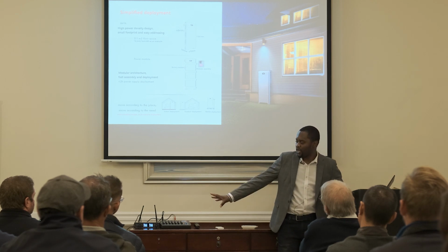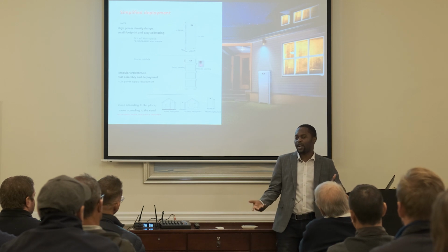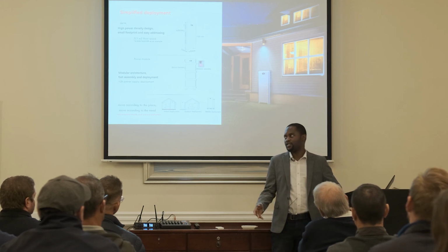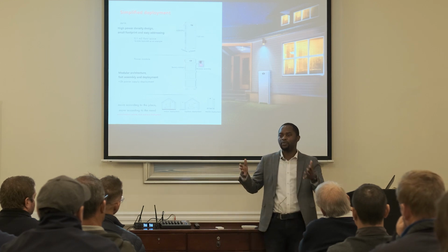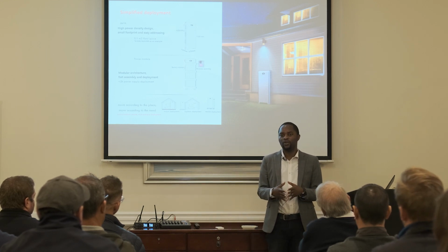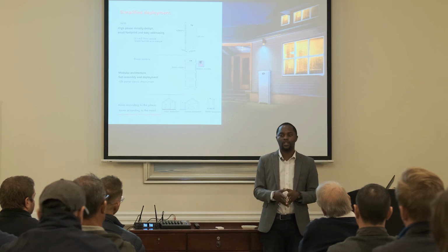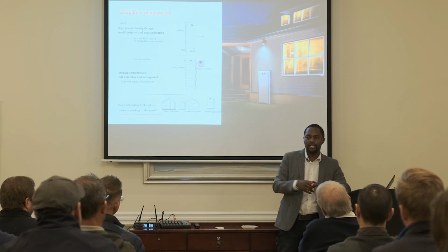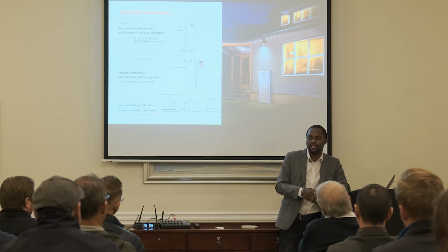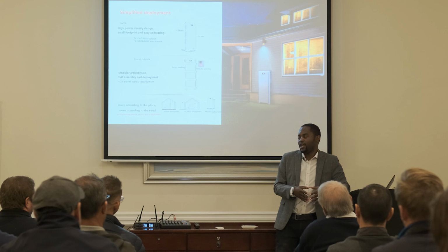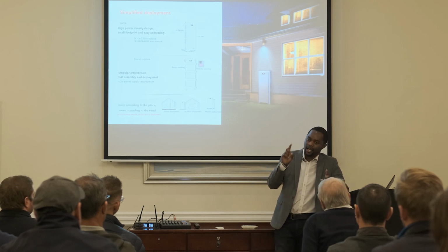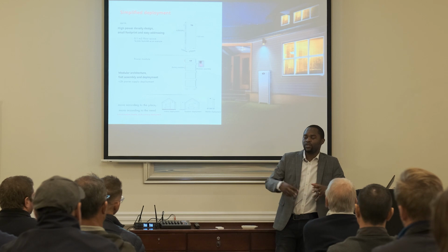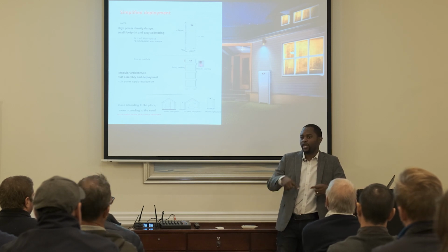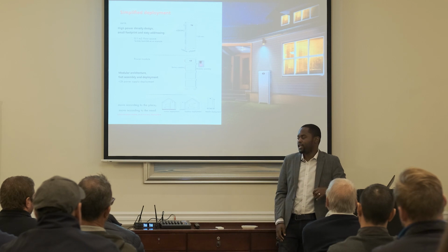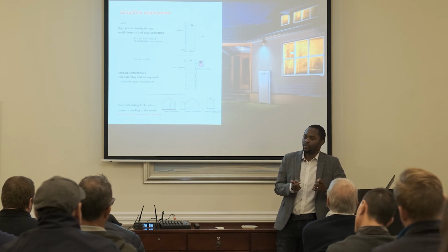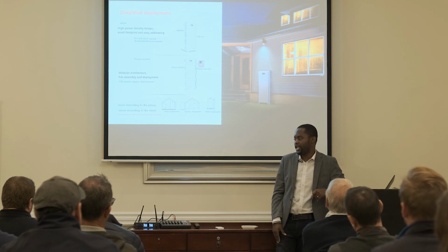So if this takes 20 minutes maybe to do, then the other 1 hour 40 minutes, we're looking at a scenario where you are splitting your DB and making sure you separate the neutrals. As you already know, the neutrals for the backup should never mix with the neutrals for the grid, right? Then you need that earth neutral bond. I understand in some other regions it's now mandatory, so you must have it. Then these inverters are equipped with that dry contact relay, so that if you want to have that externally, it's easier for you. You can wire through a relay, then your relay can change states and open and close that bond depending on the availability of grid.